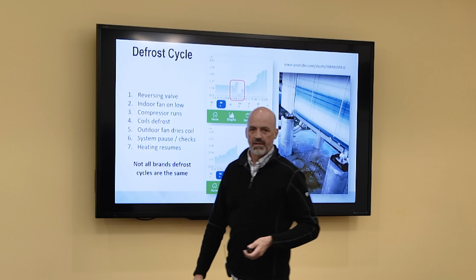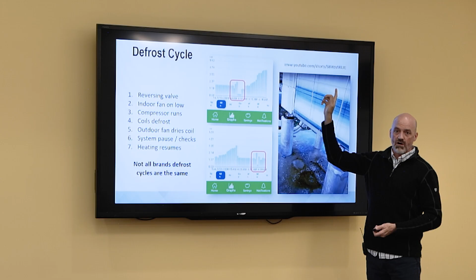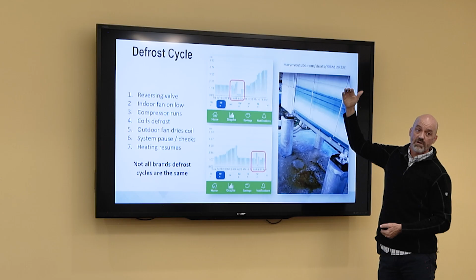Don't most of the hybrids have pan heaters? Yeah, that's a separate piece. So this coil defrost is a function of fans off, compressor on, refrigerant circuit defrosting — the loop's running backwards. It's putting itself into air conditioning mode, but without any fans on.